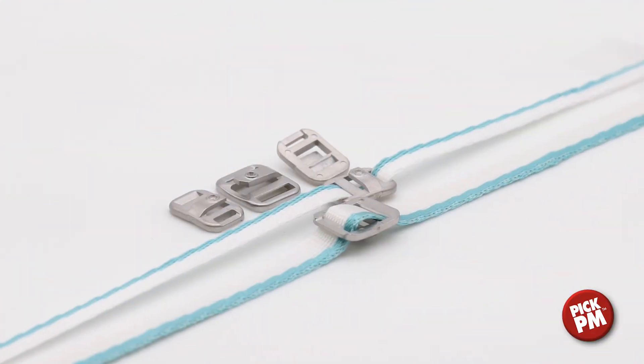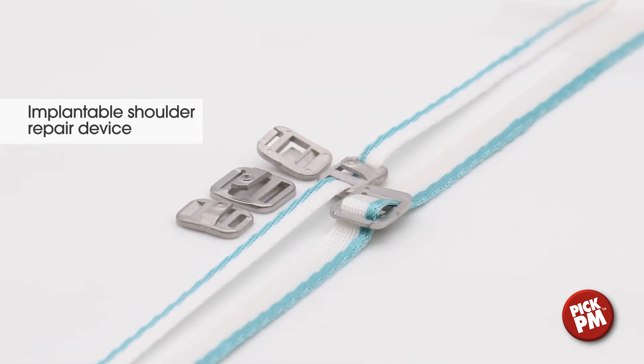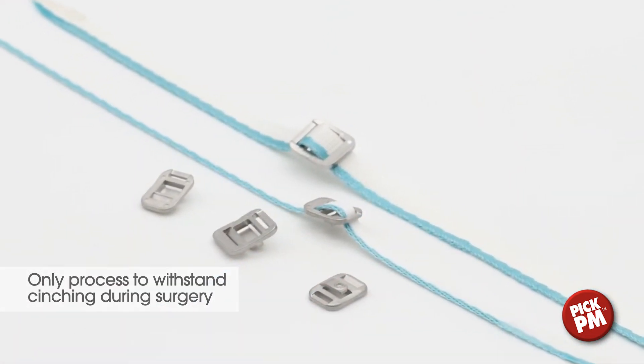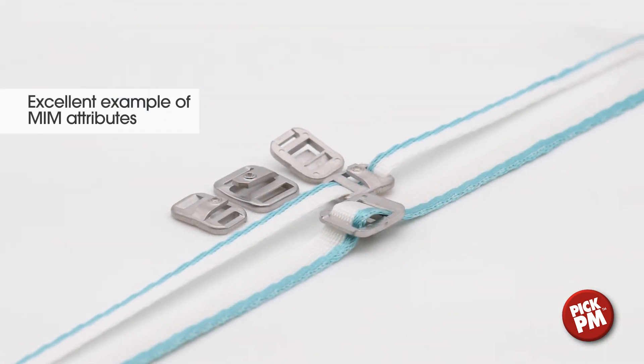Used in an implanted shoulder repair device, this buckle is made using 17-4 PH stainless steel. Several technologies were considered, but MIM processing was the only one that produced a part that could withstand the stresses induced during the cinching of the device, during surgery, and the placement of the cleat.